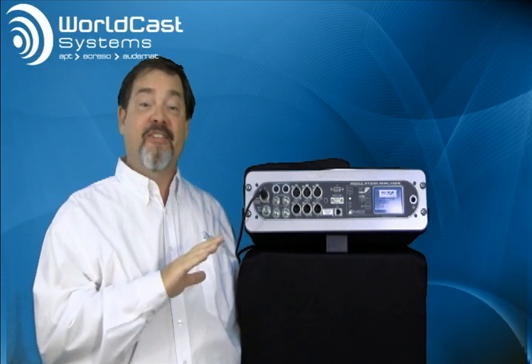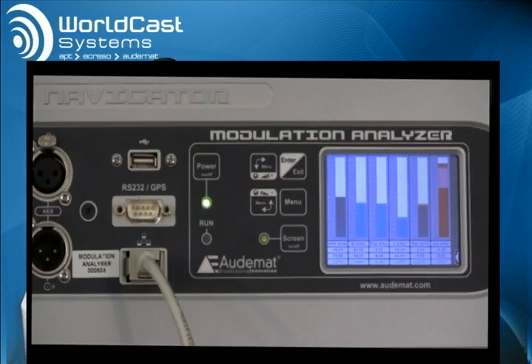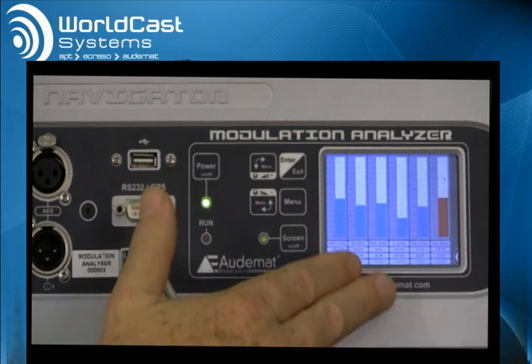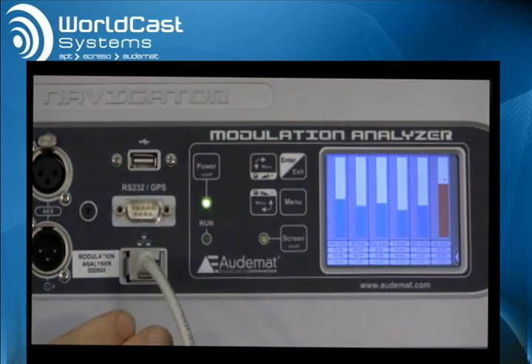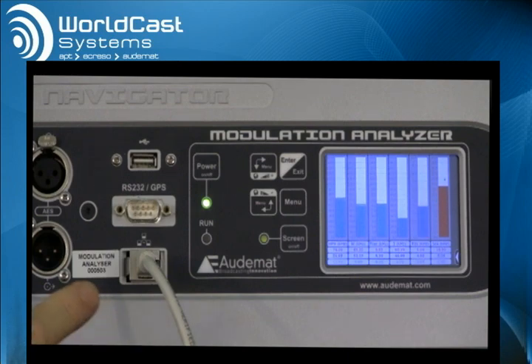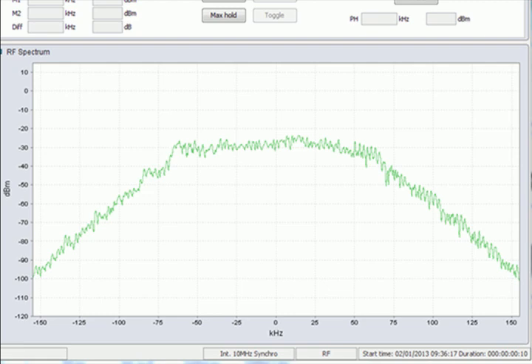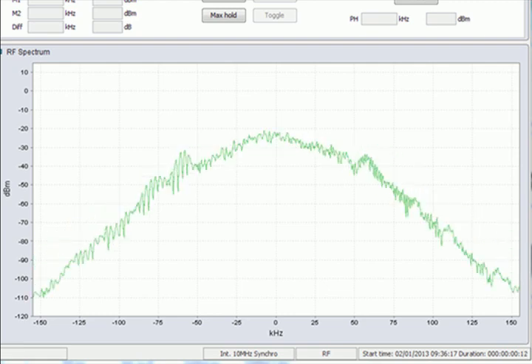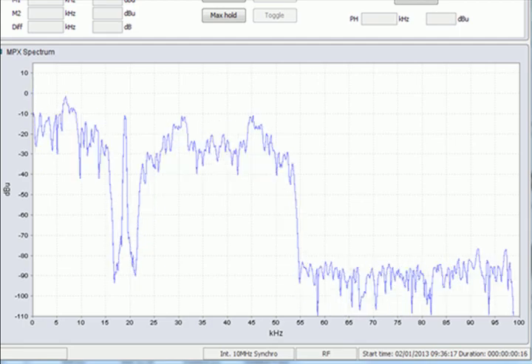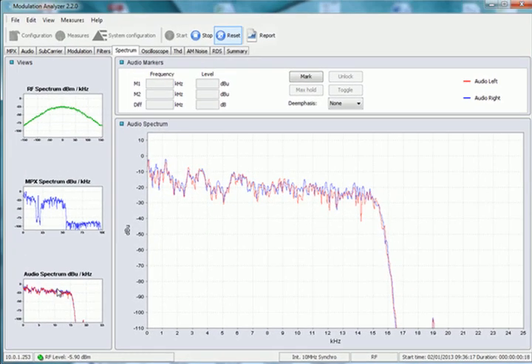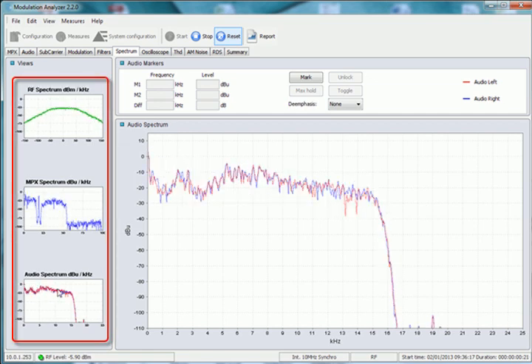The Modulation Analyzer excels at providing a lot of information in a short amount of time. All of the measurements and readings can be viewed on the embedded touch screen, or you can connect with your PC to this network port, and using the included software, you can see even more.